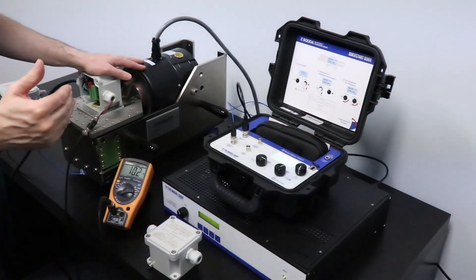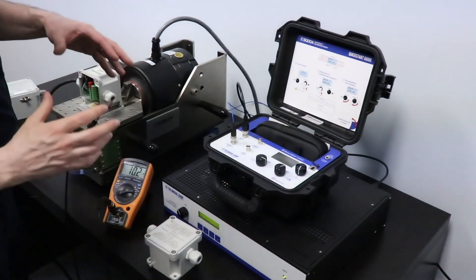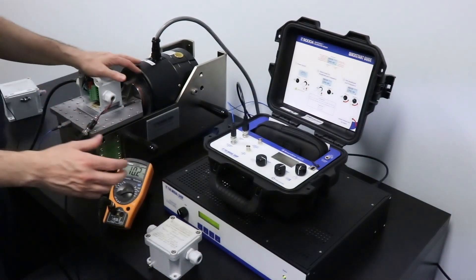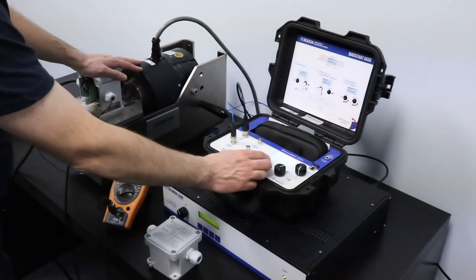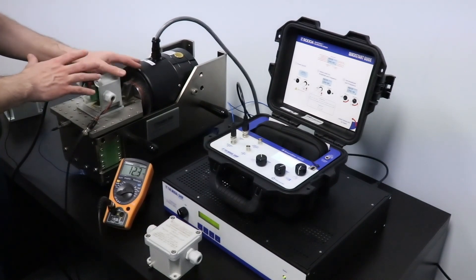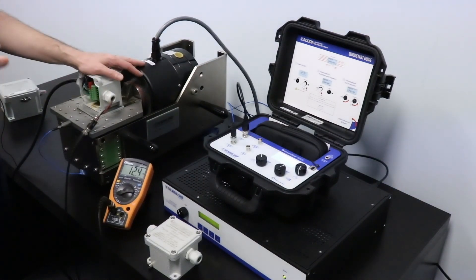So we're going to keep increasing the vibration as we go. And the critical vibration level for this particular application is one inch per second or 25 millimeters per second.